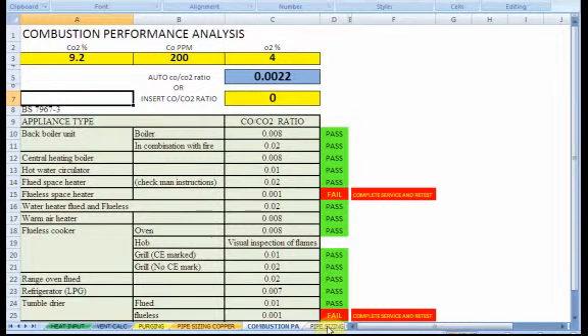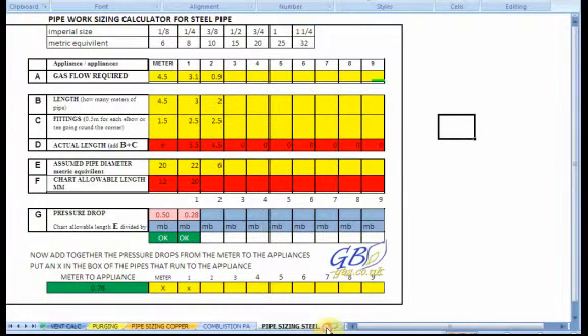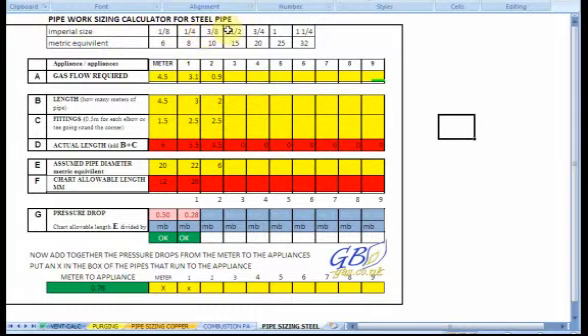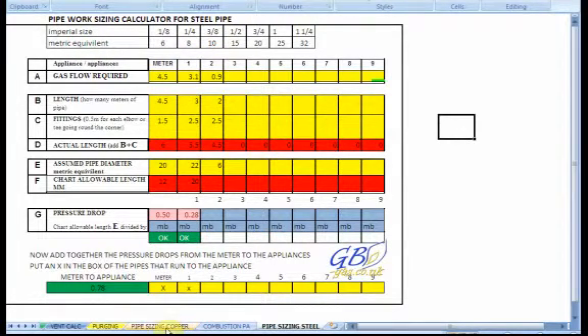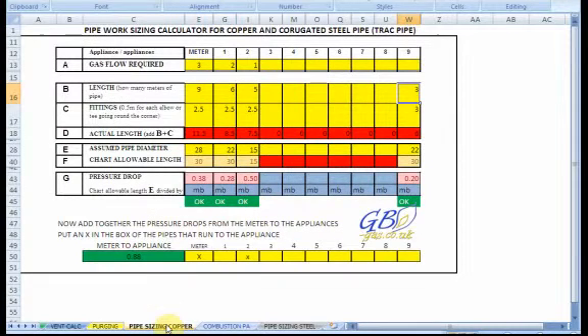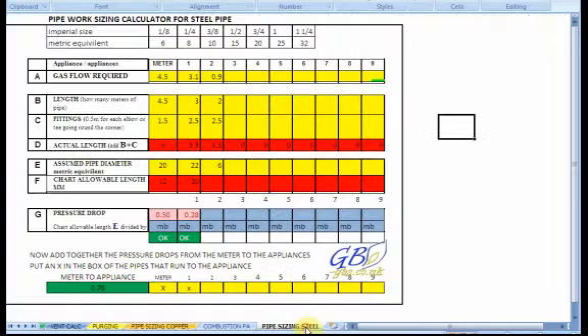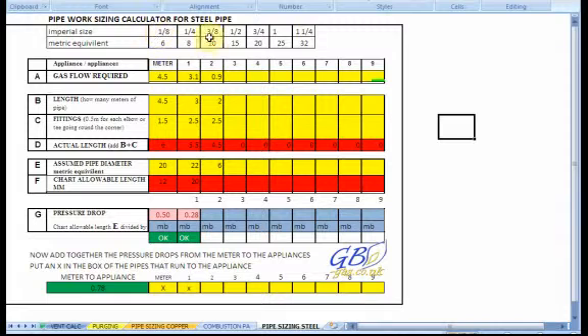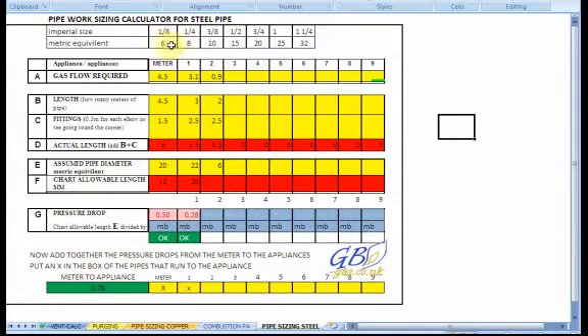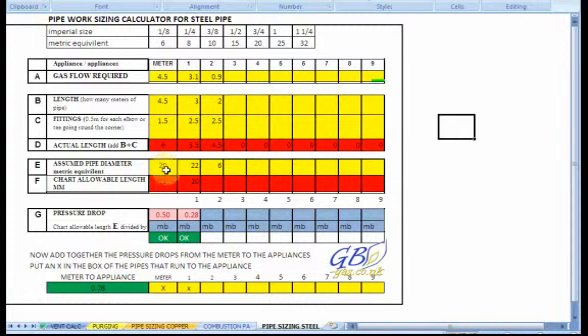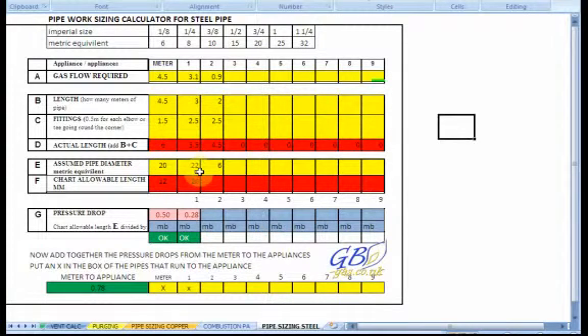The last section is pipe sizing again, but this one is for steel pipe. The calculator works exactly as it does with the pipe sizing for copper pipe. You just input your details, and it will tell you. The only difference is you need to convert your eighth quarter, three-eighths, to the metric equivalent. So, in here, we're going to use 20mm, or 22mm, or 25mm.